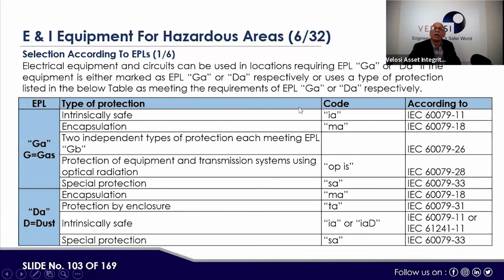The requirements of these EPLs, equipment protection levels, are defined under IEC 60079 Part 11, Part 18, Part 26, Part 28, and Part 33. These are for the gas side, and others are for the dust side. Please don't get confused. We don't expect that you should remember it, because if you have to remember it, it would be difficult. But we need to know that one of the requirements for any E&I equipment in the HAC area, the first requirement, would be what the EPL level is, what the equipment protection level is.